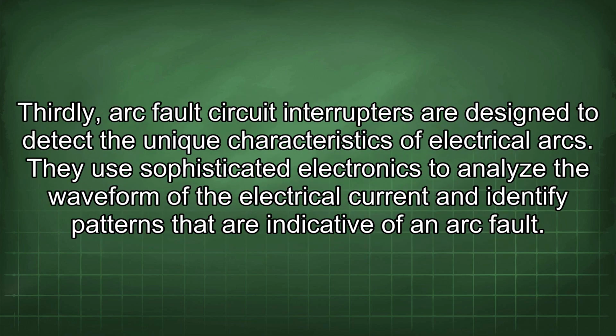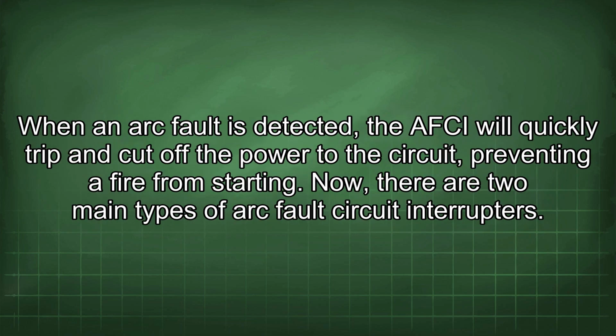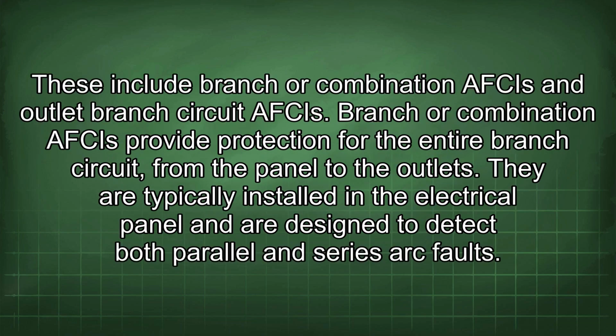Thirdly, arc fault circuit interrupters are designed to detect the unique characteristics of electrical arcs. They use sophisticated electronics to analyze the waveform of the electrical current and identify patterns that are indicative of an arc fault. When an arc fault is detected, the AFCI will quickly trip and cut off the power to the circuit, preventing a fire from starting. Now, there are two main types of arc fault circuit interrupters. These include branch or combination AFCIs and outlet branch circuit AFCIs.